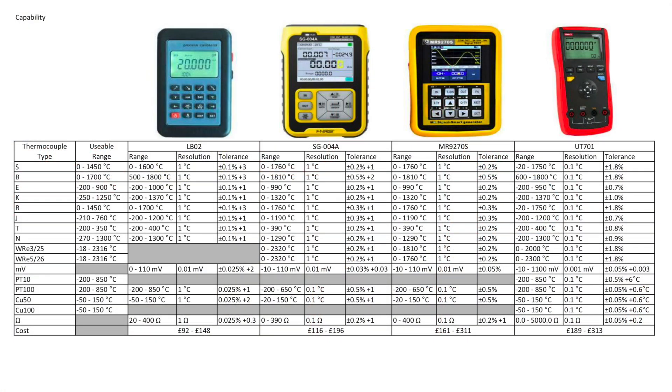So just before we do some measurements I'll put this slide up here. This is comparing the capabilities of the UT701 to my little family of cheapo process calibrators there. The LB02, SG-004A and MR9270S. You can see that it does give you all the thermocouple types and RTD types, the same as the little process calibrator units. Ranges are pretty much there. The UT701 does give you better resolution, down to 0.1 degrees C against 1 degree C for all the other units.